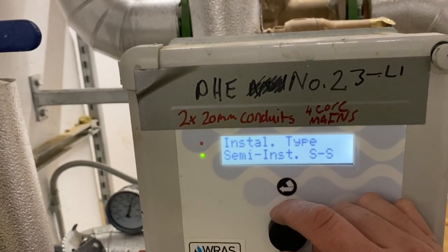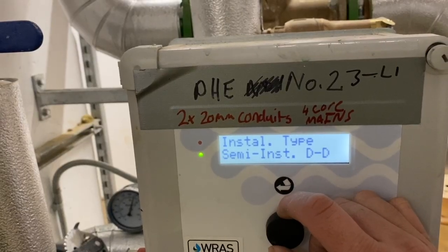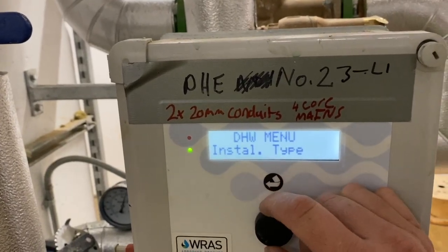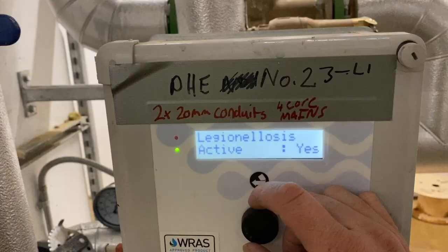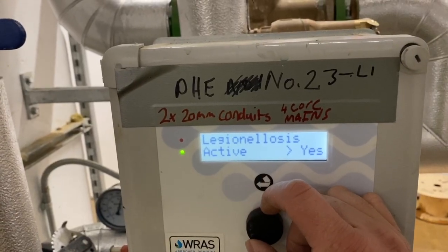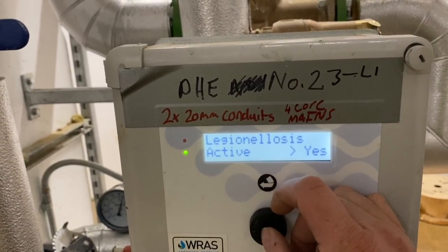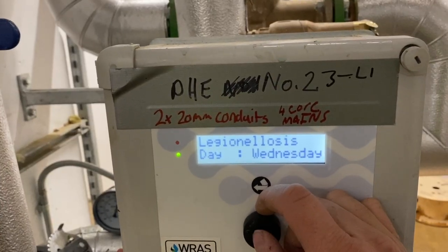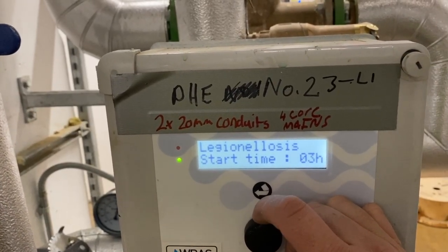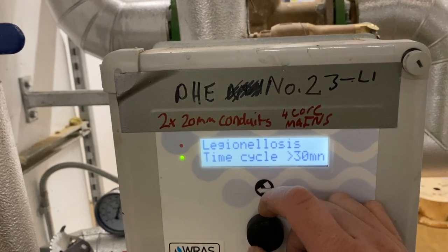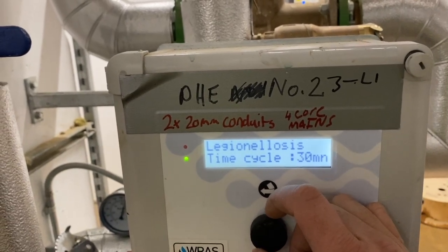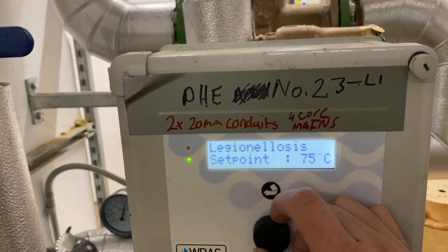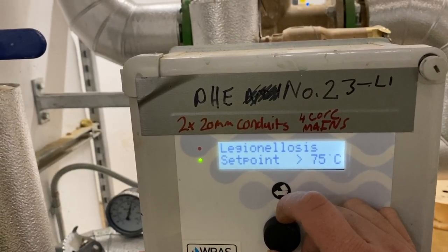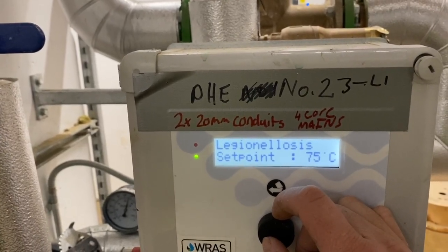So the installation type now is all relative to what pumps are on the system. There might sometimes be single, two pumps, or no pumps. Legionella, yes, we keep that on Wednesday at 3 AM as a default, unless the BMS guys are there. 30-minute cycle, we want to keep that at. No second sensor. Set point 75, we don't want to make any changes, and nothing goes above 75 degrees.